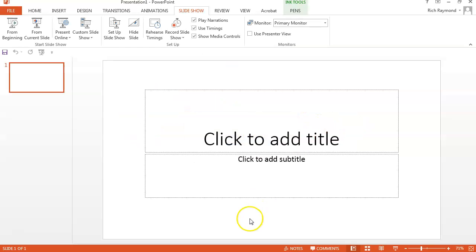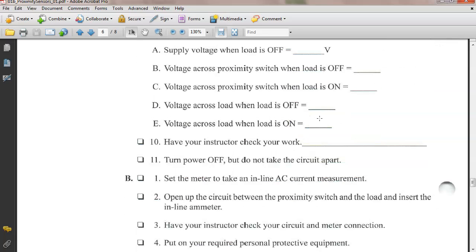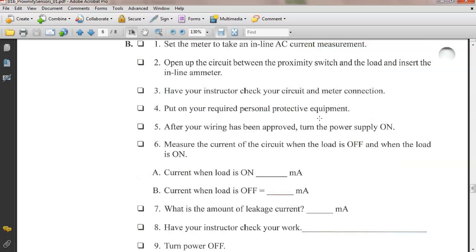What else do we have to measure? What else are you going to have to measure? Not we. It's you. We're going to have to measure current, which means we're going to have to do what, guys? We have to break the circuit, right? Everybody okay? Now, this is where people blow their fuses, because they set their meter up for current, and they get current measurements, and then when they make voltage measures, they forget to do what? Back voltage. So y'all need to be careful here.